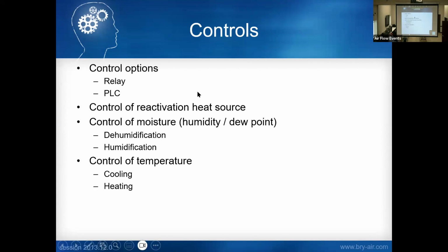We control the reactivation heat source. Again, heat sources can be many different sources, and we'll go over how we control each different type. We control the moisture level, and that's with dehumidification. We also add humidification. If it's a very critical environment, they've got to be at 35% RH plus or minus 1% RH, and bringing in all outside air in the winter, you may have to add moisture. So we do package with humidification as well. How do you control dehumidification? Do you modulate the burner, modulate the wheel speed? I've got a slide here. Shortly after that, yep.